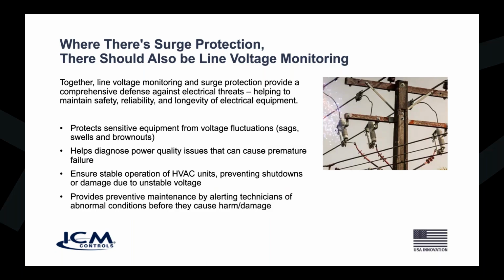It also will ensure more stable operation of the equipment, preventing shutdowns, and with built-in anti-short cycle protection can prevent short cycling due to power losses going on and off, on and off. We also provide preventative maintenance to your equipment by alerting a technician of an abnormal condition. So when they go out and look at a piece of equipment that has one of our voltage monitors in it, and it's in an alarm mode, they're going to say, hey, there's something wrong here. You're going to call out a technician because your unit's not working. They're going to see the ICM voltage monitor in there, and they're going to say, oh, wow, I see what the problem is, and they're going to be able to fix that problem and get you back up and running.